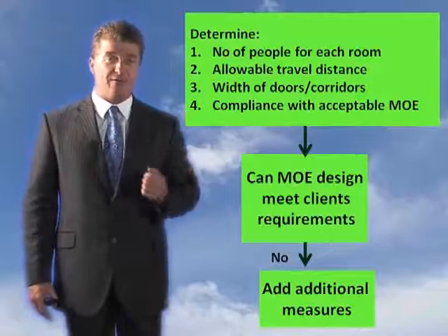So now you're asking for flexibility. Now this code is allowed to be flexible, and what it says is you can vary it in 3 ways. First of all, you can put sprinklers in. Now, if you put sprinklers in, it reduces the risk profile by a factor of 1. An A3 becomes an A2. An A2 becomes an A1. A B3 becomes a B2. That's the first thing you can do. The next thing you can do is you can put early warning in, or you can have a high ceiling. These are the 3 things. You can do 1, 2, or all of them.